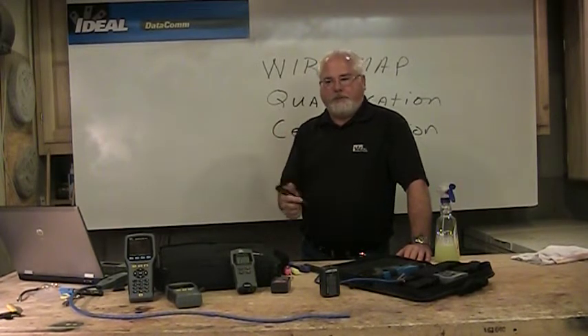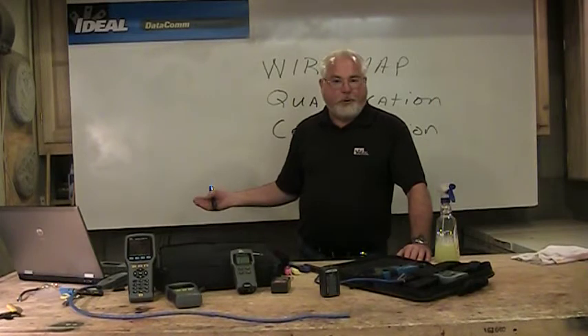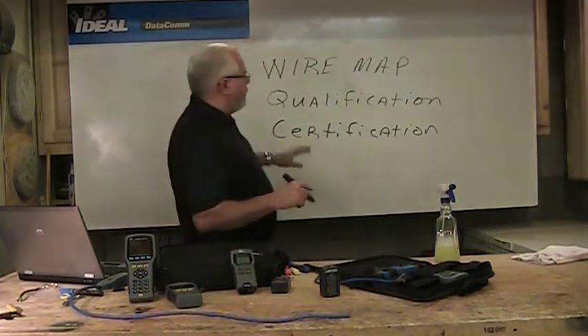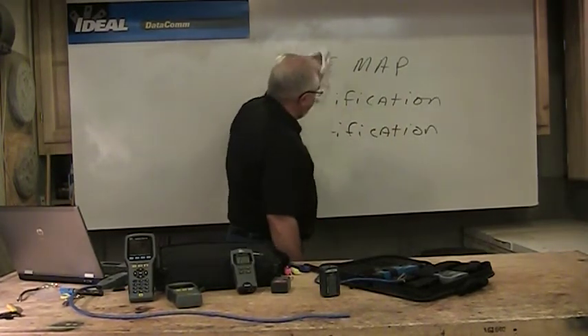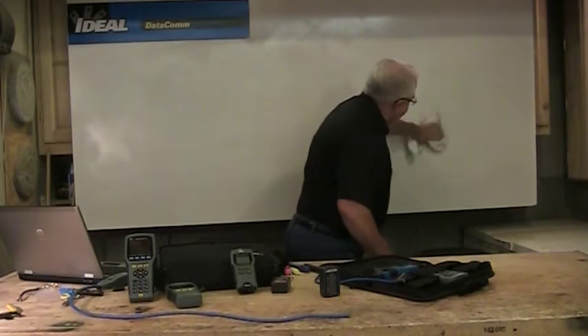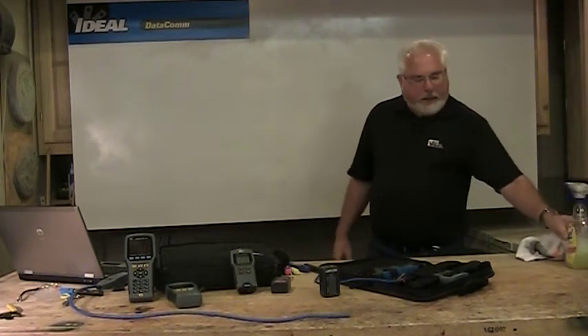If you're doing a large commercial job and the builder is asking for certification, they're asking you to test the cable to a certain standard — Cat6, Cat5e, 6A, whatever it might be. These certification testers do a lot of high-frequency testing and they get pricey. You can spend $7,000 to $10,000 real quick, especially if they do fiber as well. Certification testing is usually on the higher-end jobs; in some cases it would be total overkill, like in a residential home. So wire mappers run $50 to $100 and can go up to $300 to $400. Qualification testers run $1,000 to $3,000, and certification testers are roughly $8,000 to $10,000 and above.